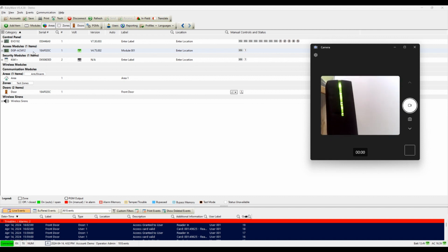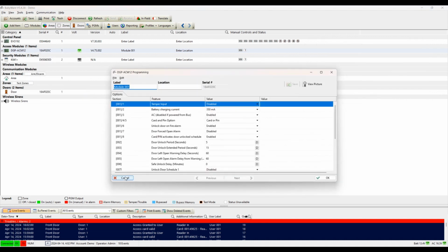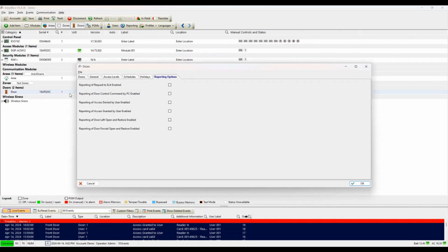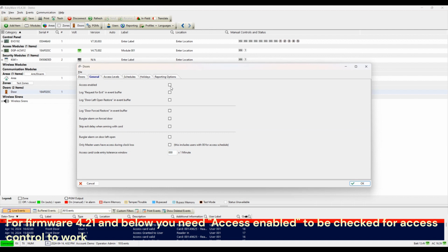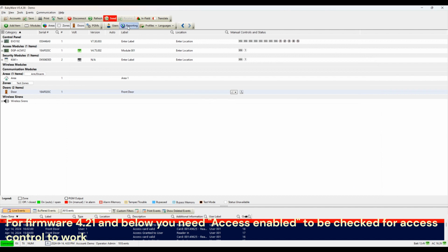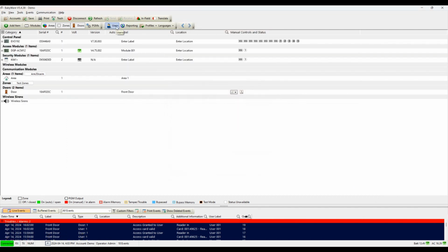So going back to the ACM. Sorry, in the door options, I like here under general, I like to have this access enabled, because sometimes, for older versions, for previous versions of the ACM firmware, if you don't have this option enabled, your access will not work.